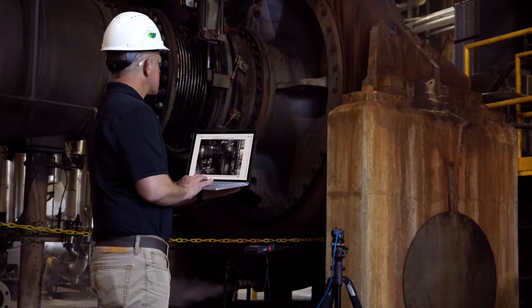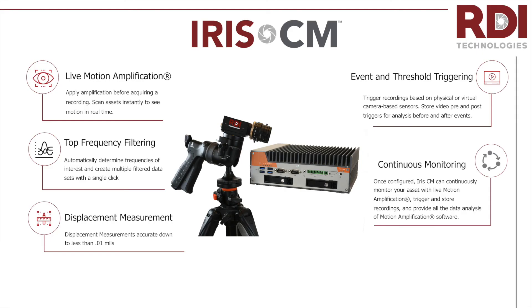The Iris CM takes all of the power of our technology platform and puts it into a continuous monitoring system capable of continuously monitoring your assets with 24/7 coverage, with live motion amplification and triggered recordings using virtual video-based sensors or connected external sensors like accelerometers, 4 to 20 milliamp signal, and tach-based speed triggers. This powerful system can be used as a simple one-camera monitoring system or can be combined into a powerful fully scalable multi-camera network solution that monitors an entire facility in real-time with notifications and alerts.